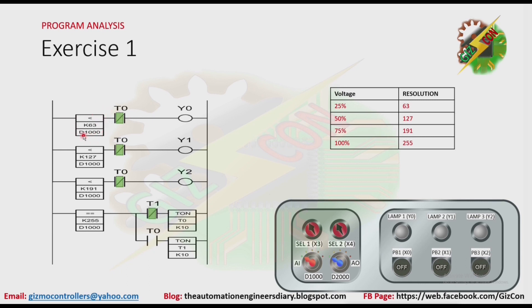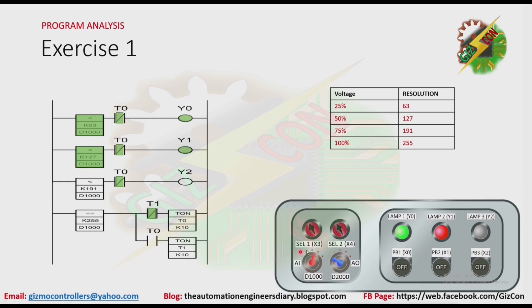As you can see here, we have a comparison. If 63 is less than the value at address 1000, which is the address of the analog — 63 represents 25% — now if this condition is satisfied, Y0 will turn on. And the same with the other values. The value of the analog at address 1000 is more than 25%, the condition is satisfied, that's why Y0 is on. Now the analog value is more than 50%, this condition is satisfied, that's why Y1 is turned on.